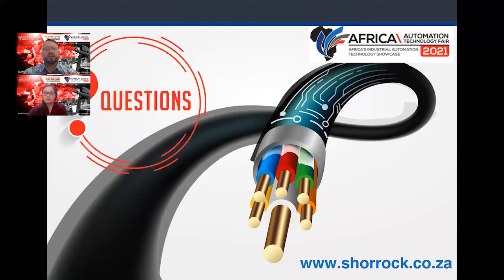But with this, we can actually get diagnostics from it. We can see the actual current of that panel at that stage. And we can also monitor that and see if the current starts increasing over a period. It could be that we have instruments down the line that is busy giving problems or busy failing or losing efficiency. And this could all be monitored over time.